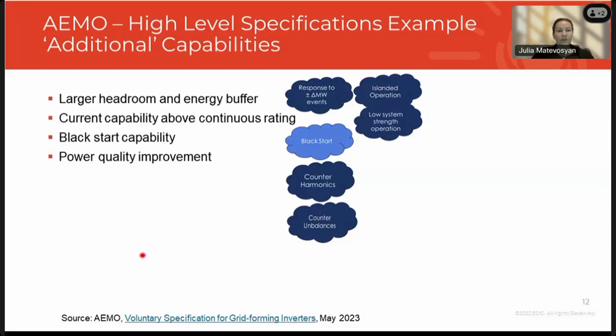In terms of additional capabilities, they define that maybe larger headroom, energy buffer would be helpful. Current capability above continuous rating could be helpful, and that speaks to low system strength operation, but maybe also island operation, and restoring grid from a blackout. That's where this higher continuous current capability may be helpful. Black start capability from some of the resources and power quality improvement. So AEMO underlines that these requirements are in addition to the core requirements, and maybe not all resources will be needed to provide that.